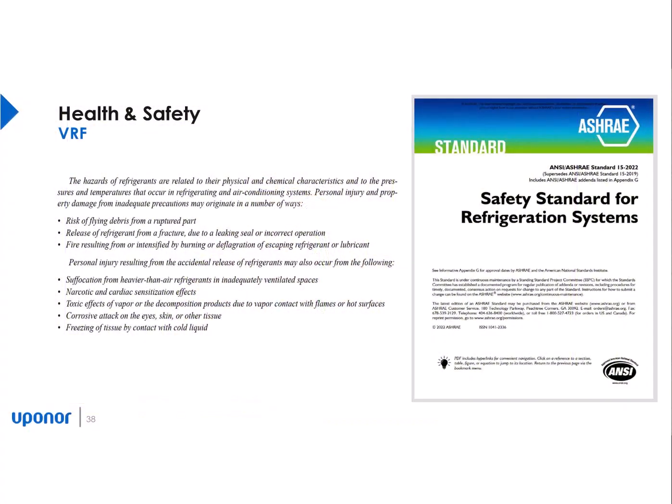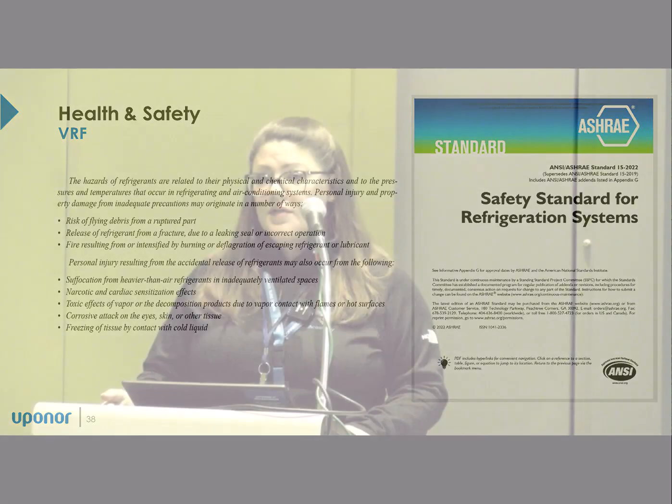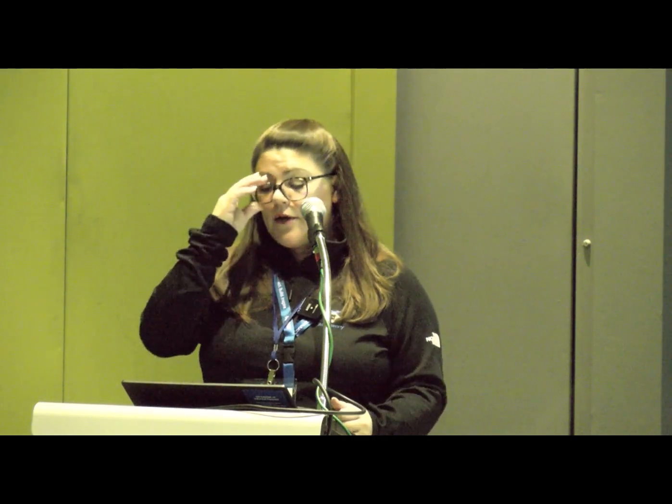For this reason, ASHRAE Standard 15 limits the refrigerant volume based on the smallest space served. So people who are designing VRF systems should verify that the amount of refrigerant that could possibly leak and the smallest space into which the refrigerant could accumulate are in compliance with this standard. Properly addressing the risk of refrigerant leakage requires extensive design considerations, added costs such as refrigerant detectors, separate systems for smaller spaces, piping rearrangement, etc.